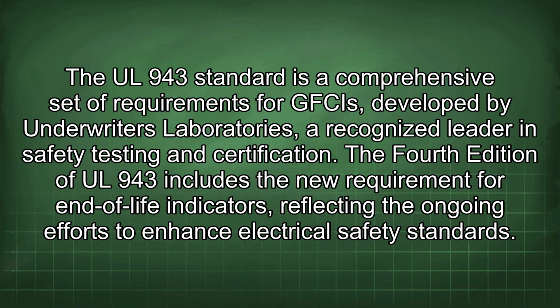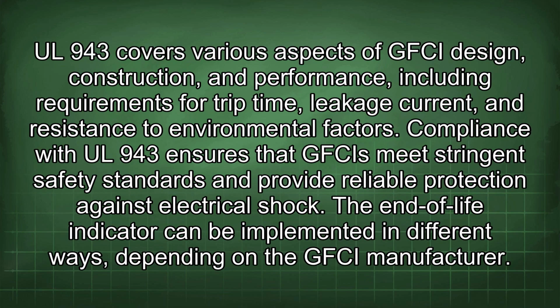The UL 943 standard is a comprehensive set of requirements for GFCIs, developed by Underwriters Laboratories, a recognized leader in safety testing and certification. The 4th edition of UL 943 includes the new requirement for end-of-life indicators, reflecting the ongoing efforts to enhance electrical safety standards. UL 943 covers various aspects of GFCI design, construction, and performance, including requirements for trip time, leakage current, and resistance to environmental factors.